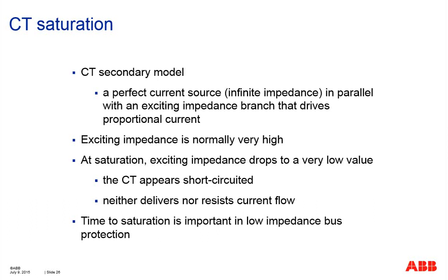However, we have to understand that for a properly sized CT, according to your power system characteristics, your source impedance, everything, if you run proper source studies, the CT may saturate under external fault, more or less, but it should not saturate right away. For any properly sized CT, you should allow a certain time in milliseconds in which the CT can authentically reproduce the secondary current for the relay. Okay, that's very important.